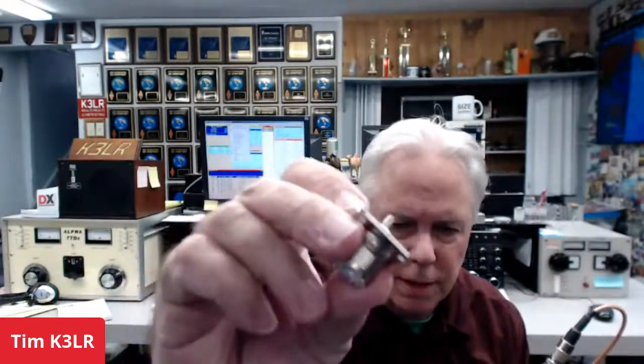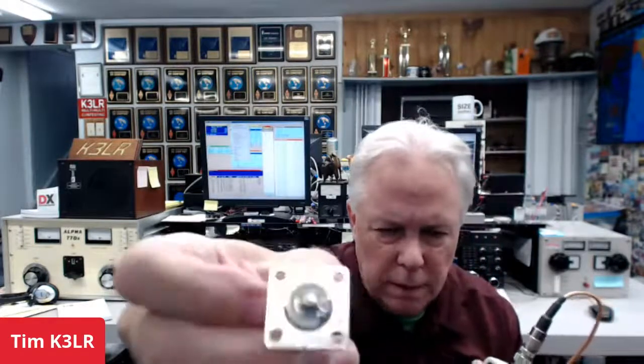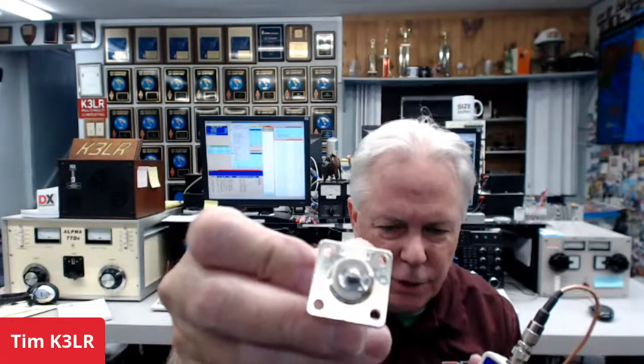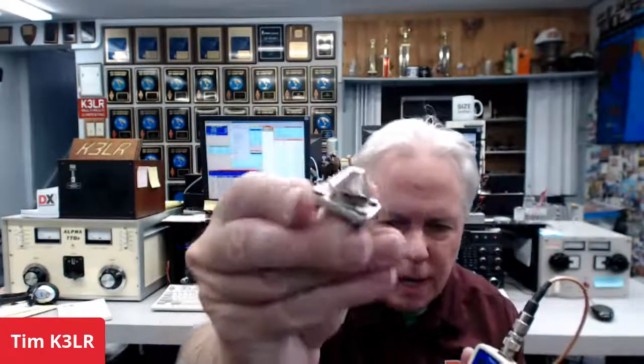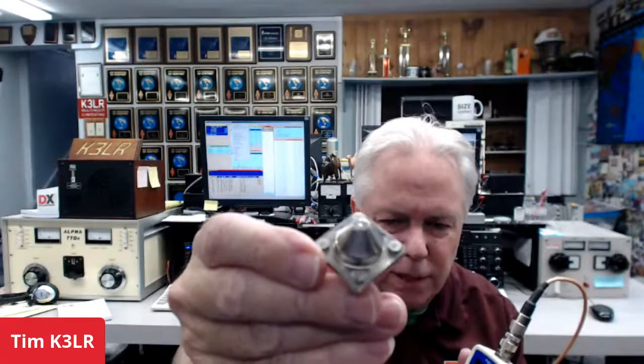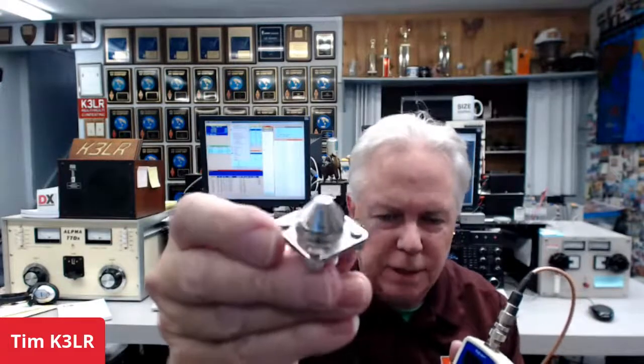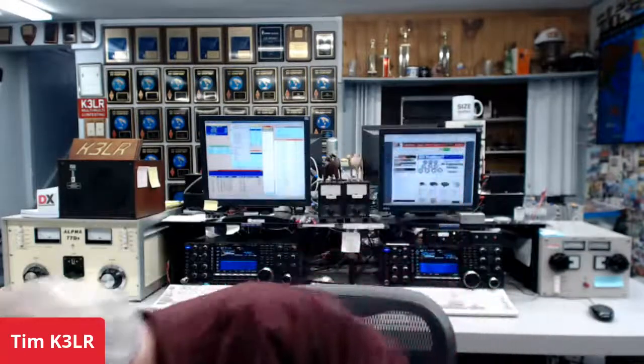Okay, so I have an open here. Here's my open. It's just an SO239 with nothing connected to it. I have a short. So you can see that the center conductor is shorted to the outside. So that's the short. And then I have a 50 ohm load. And underneath this cap is a 50 ohm high precision resistor. This is perfectly 50 ohms. So those are the 3 things that I have to have to move the reference plane to calibrate to here. And so we're going to hit the check mark again.